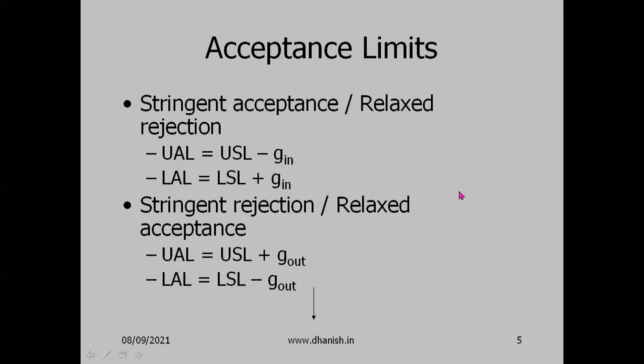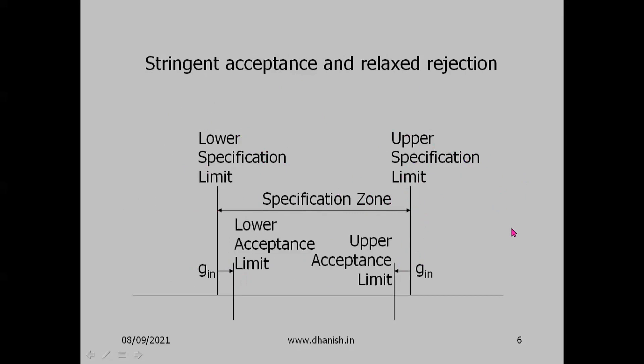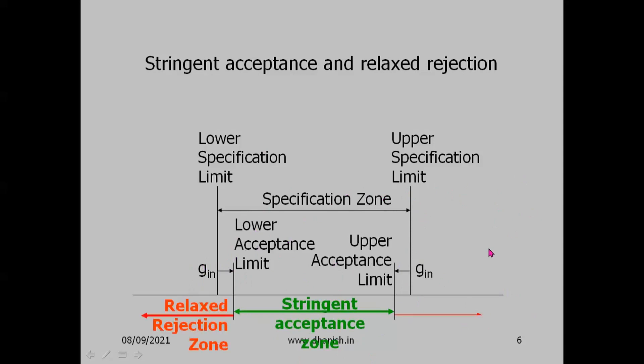Graphically, for stringent acceptance (relaxed rejection), the guard band is inside the specification zone. The upper and lower specification limits are reduced by an amount equal to the guard band — expressed as a percentage of the expanded uncertainty — to obtain the lower and upper acceptance limits. The specification zone is effectively reduced by the guard band to get the stringent acceptance zone.